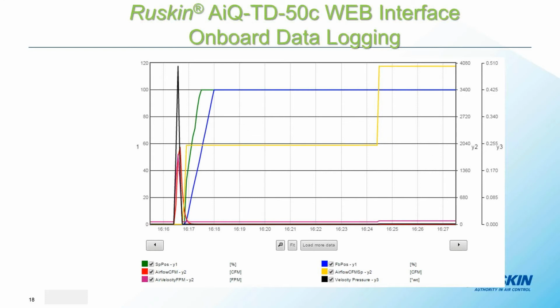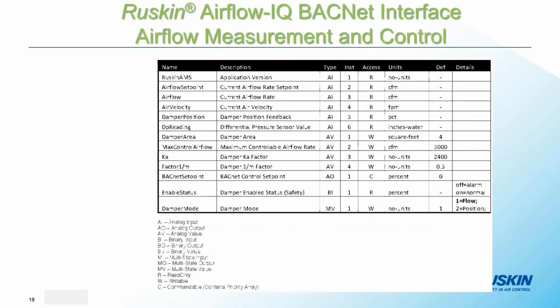But things that we're seeing here in this trending, it shows us what our set point position was, what the feedback position was from the actuator in terms of percent commanded. It shows the airflow CFM, shows the airflow velocity, it shows the airflow CFM set point, and it also, not applicable here, but would show the velocity pressure that we were getting. So all of that information is logged, and you really don't have to do much more than that.